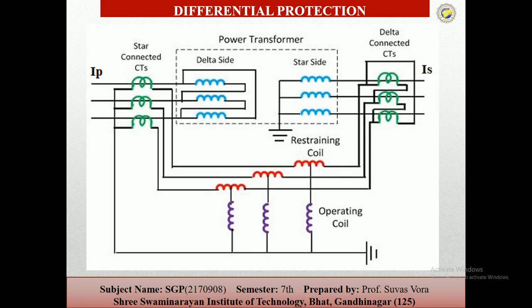When an internal fault occurs, the operating torque becomes more than the restraining torque, and then the tripping circuit contacts close to open the circuit breaker. The restraining torque may be adjusted by varying the number of turns of the restraining coils. Here you can see the power transformer is connected, with CTs on the primary side and the secondary side. Both the CTs are connected with the restraining coil, this restraining coil is also connected in parallel with the operating coil, and the operating coil gives the signal to the circuit breaker.